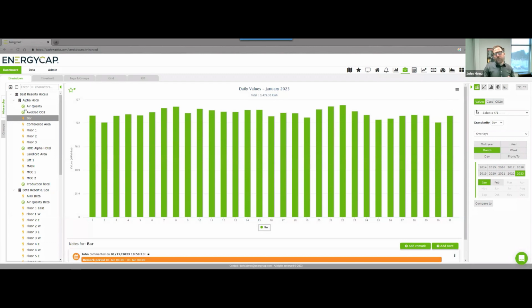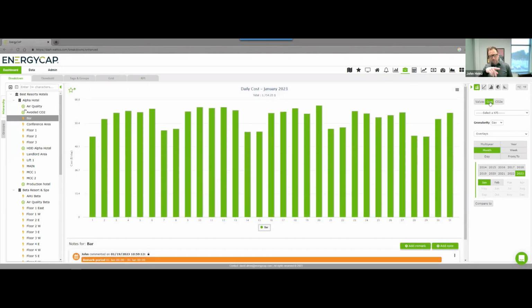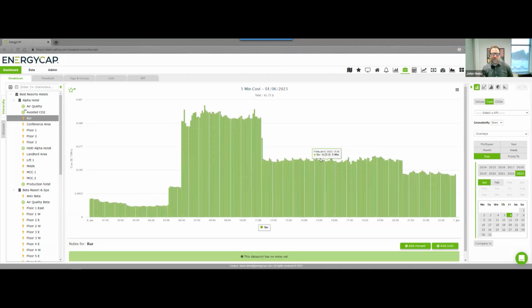The system's tracking use and demand. There's a tariff engine which also allows you to apply cost and CO2 calculations, so for any object you're tracking, you can apply cost to it, including time-of-use rates. Because you're tracking interval data, you can track time-of-use rates and get your real-time cost. If I go to, let's say, a daily profile, this shows every 5 minutes what my cost is, because it takes the rate I built, applies it against the consumption, and gives me my 5-minute cost, then rolls it up—in this case, I'm looking at a daily view.